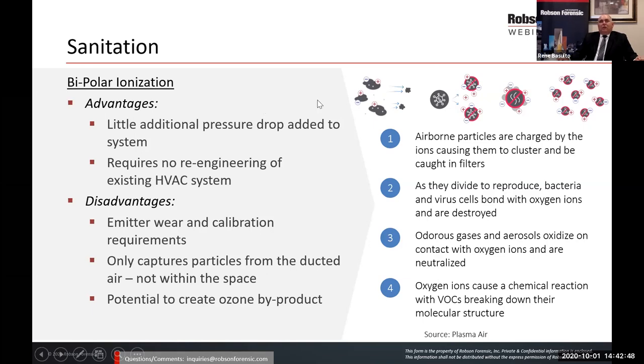But it's interesting. We do a lot of work on my engineering side for the school district, and we do most of the plan review and inspections for the school district. So we review other engineers, and we assist the district in developing their criteria. Their criteria post pandemic, they were actually installing these bipolar ionization units inside the air handlers and air distribution systems in their schools in an effort to reduce the amount of outside air into the buildings. Again, remember I said that outside air equates to energy costs. So they were trying to reduce the energy cost by reducing the amount of outside air, and they were using the bipolar ionization to justify and perhaps clean the air out to reduce that outside air. We're rethinking that right now.